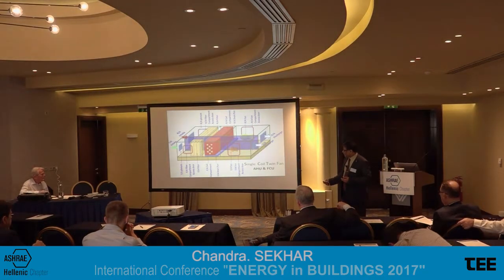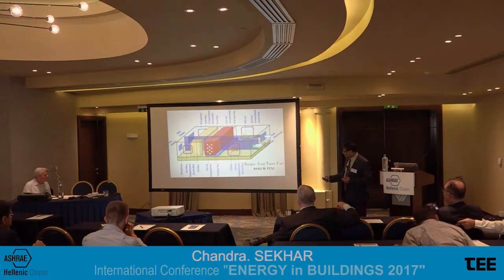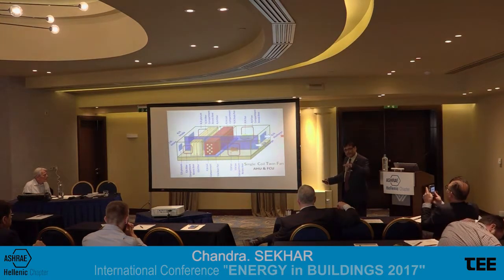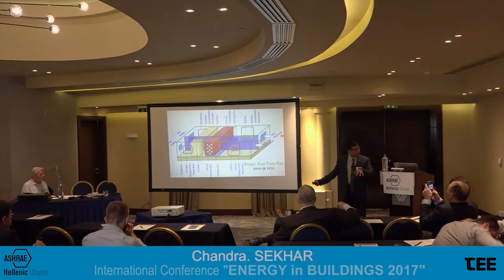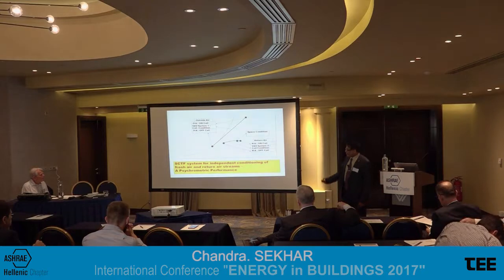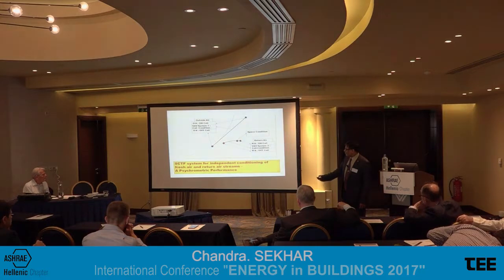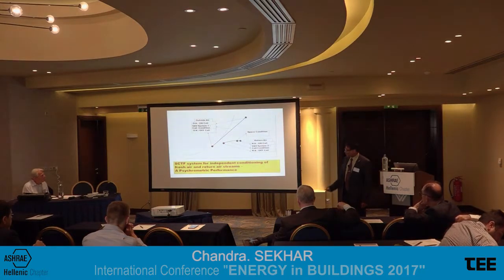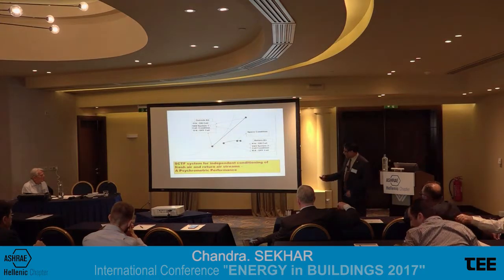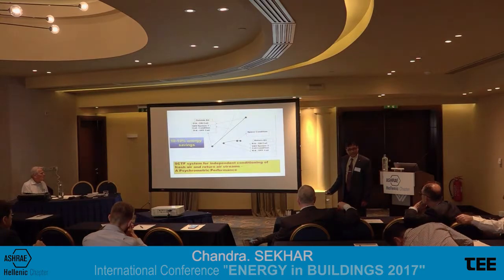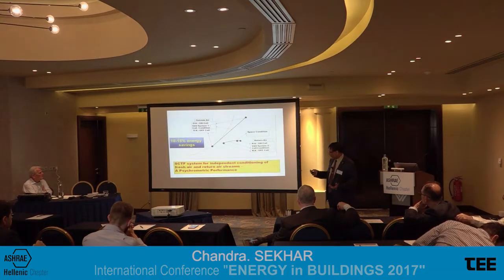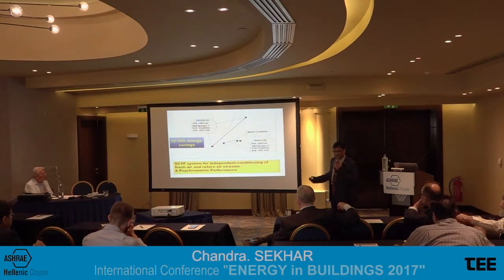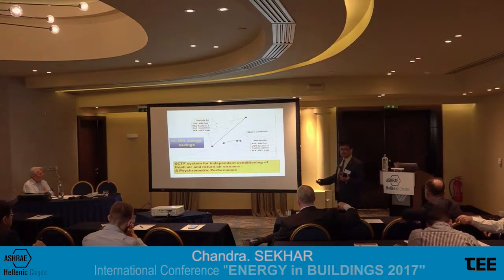So this is just a simple animation that showed that the two air streams don't mix. We transport them separately, and the mixing actually happens in the occupied zone based on the local demand. Now what does that do? Psychrometrically, we handle the outside air, pull it down to the right temperature and humidity, and this part here, recirculated air, is only for cooling. And this is mixed at each zone depending on what the loads are. Does that save energy? Sure it does. And how do we compute this energy saving? For the simple reason that we don't need to take any more outside air than absolutely necessary. It's on demand at all times based on what the occupant needs are.